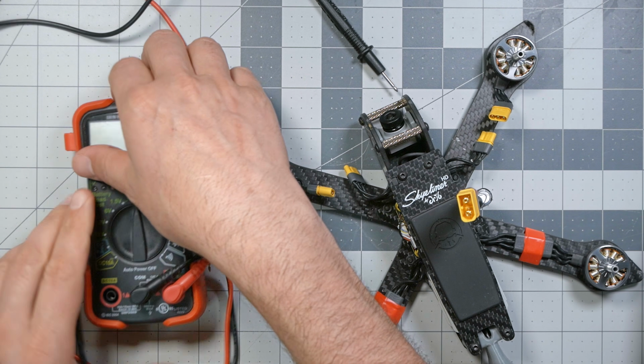The takeaway is that you cannot use a multimeter to test for short circuits in a DC brushless motor, at least not the kind most of us have. You need a very sensitive multimeter that can measure down in the milliohms, or something called an inductance or Henry meter, which can measure the inductance of the motor coils to tell you it's bad.